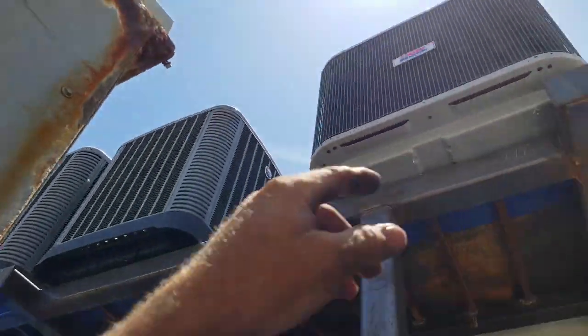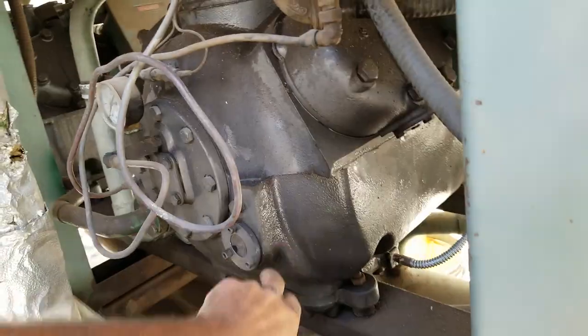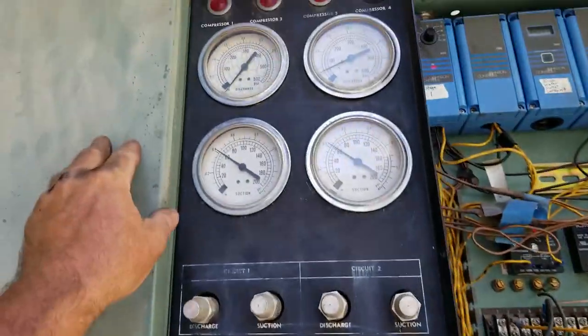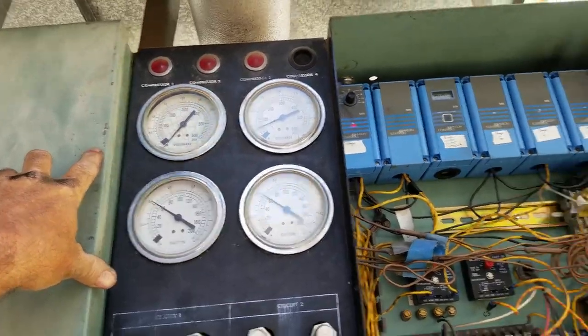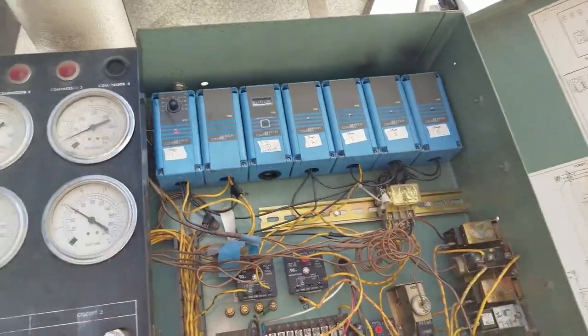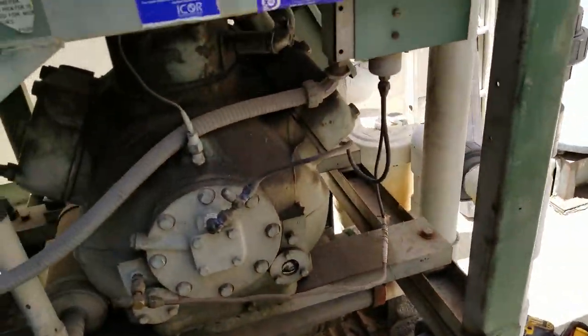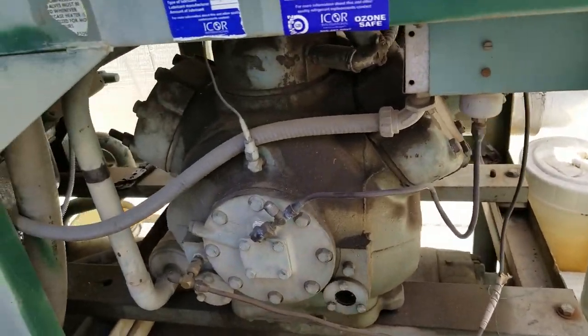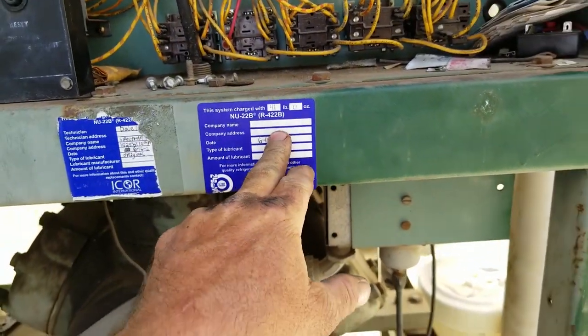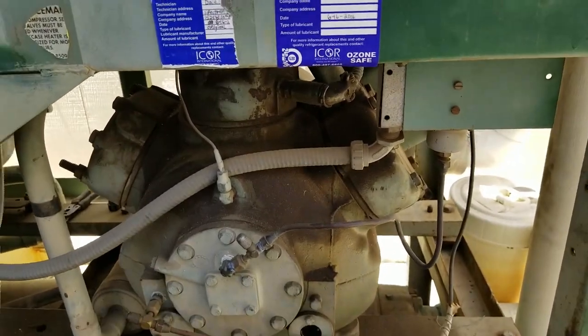At least they're not Goodman units up there — it's a Heil and two Ruud units. Look at this old-school thing, it's a 1990 unit but it's obviously been worked on. My static pressures are like 50-something psi on R-422, which comes out to be about 30-something degrees.